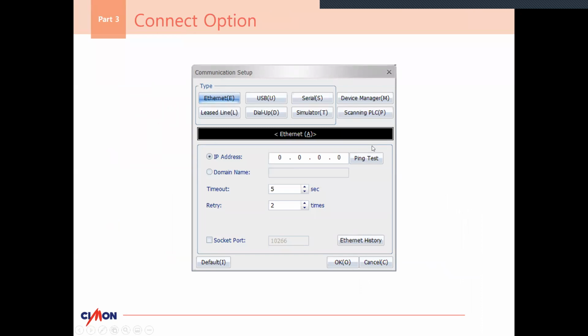When we talk about connect options, we're going to be dealing with the simulator today, as we've already discussed. The top three I would use; the bottom two, I'd ignore - though if you do use those, all the more power to you, we won't cover those today. The top three: we have Ethernet, which is set up after you've already connected to your PLC once, either via USB or serial, and then you'd program the Ethernet IP once you've established communication. The USB is a USB to USB mini B, not mini A or mini C. The serial communication supports RS-232, 485, and 422.